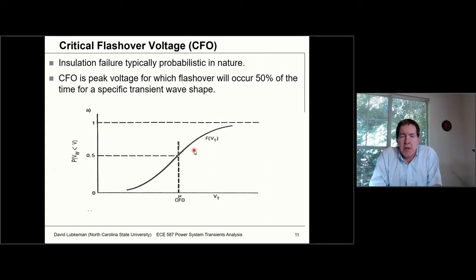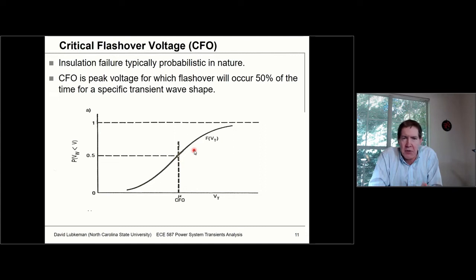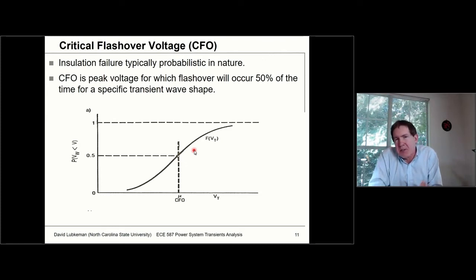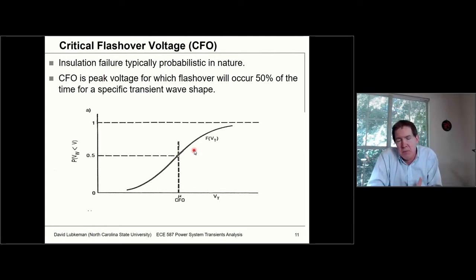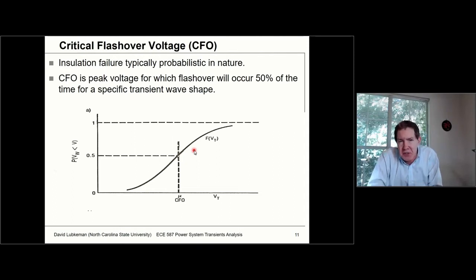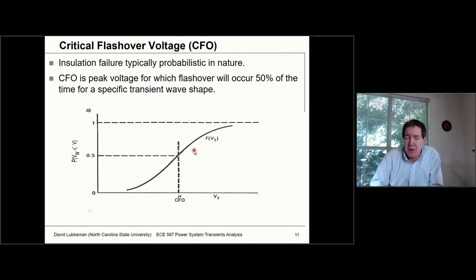Whether a flashover occurs or not is defined by the critical flashover voltage. If you're testing a circuit breaker withstand to surges in a high-voltage lab, hitting it with 100 kV pulses, a certain number of times it fails and a certain number of times it doesn't — depending on conditions like the number of free electrons around the insulating devices. Critical flashover voltage is the peak voltage at which flashover occurs 50% of the time. If you run a series of tests with the same waveform and find the 50% point, that's your critical flashover voltage.